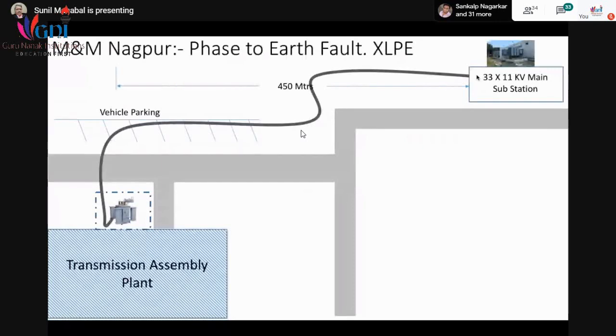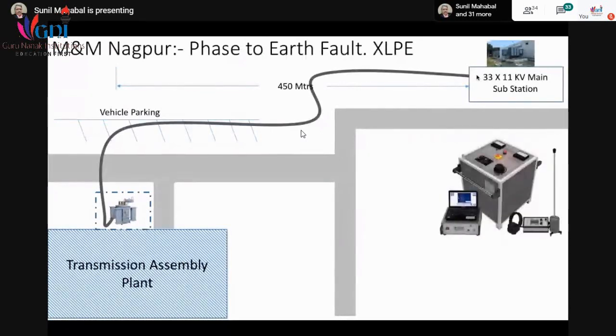So we decided what we could do now, because only one cable was available there. So we called that unit, which is for testing underground cables for faults. How does this unit work? It actually gives the voltage in impulses. For example, if the cable is meant for 11 kV, then with the dimmer you can vary the voltage to the cable in phase. So once you know which phase is faulty, then on that particular phase only you can inject the voltage, and that voltage can be varied.